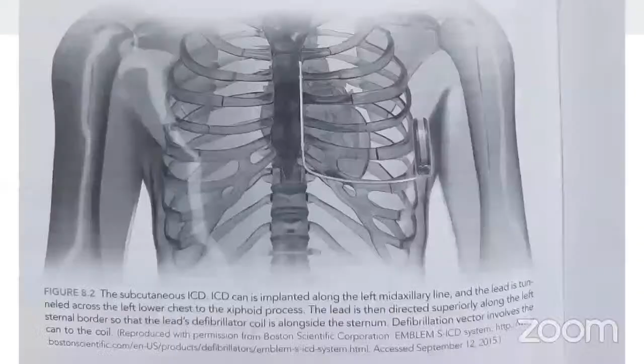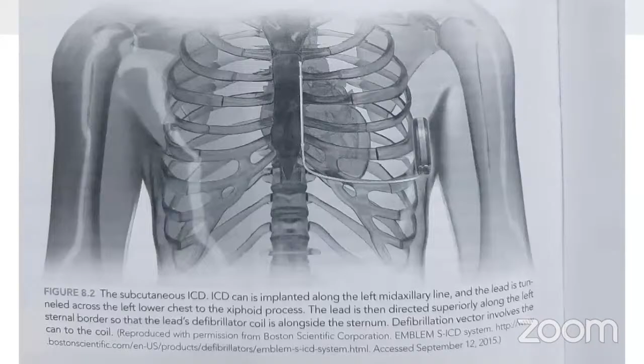The subcutaneous ICD is implanted along the left mid-axillary line. The lead is tunneled across the left lower chest to the xiphoid process. The lead is then directed superiorly along the left sternal border so that the defibrillator coil lies along the side of the sternum. Here the can acts as a cathode and the defibrillator coil acts as an anode. So, X-ray feature showing the ICD.